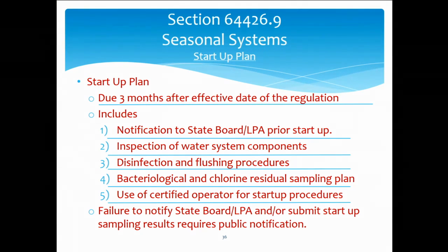You have to notify us prior to startup. You have to inspect all the system components. You have to disinfect and flush, the flushing procedures, bacteriological sampling and chlorine sampling. You have to use a certified operator for startup procedures. And failure to notify the state board or LPA and or submit a startup plan, sampling results is a violation.